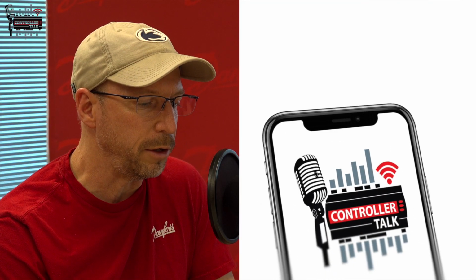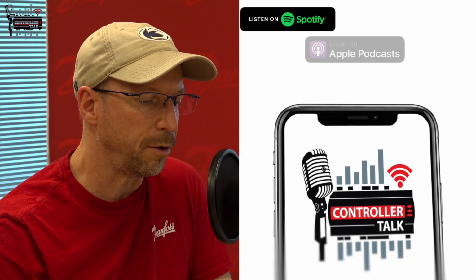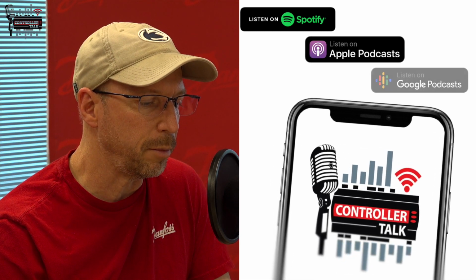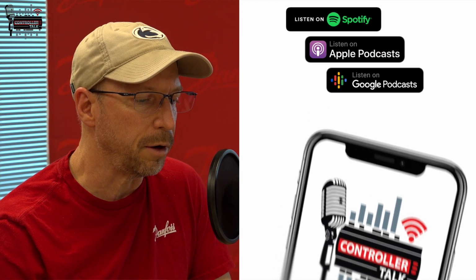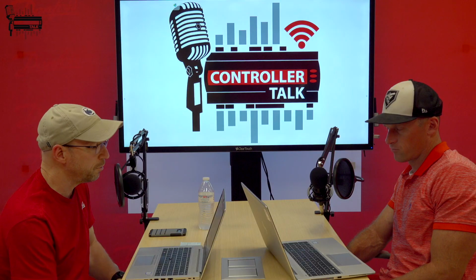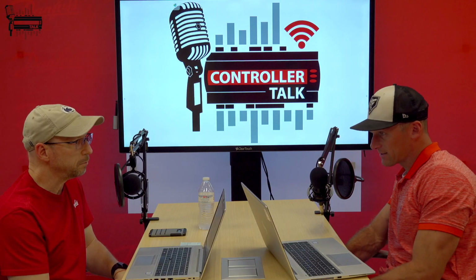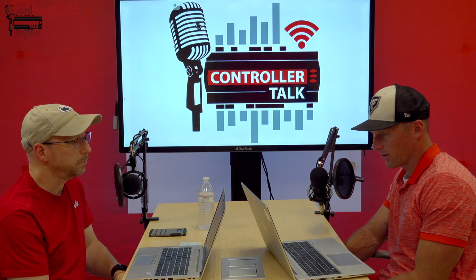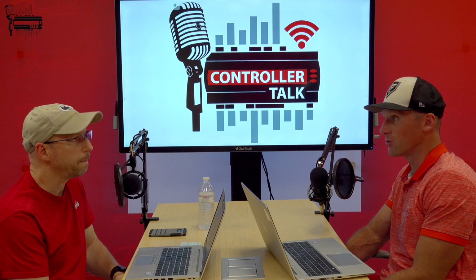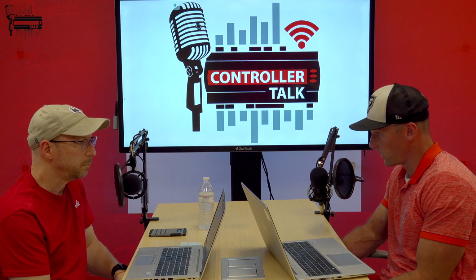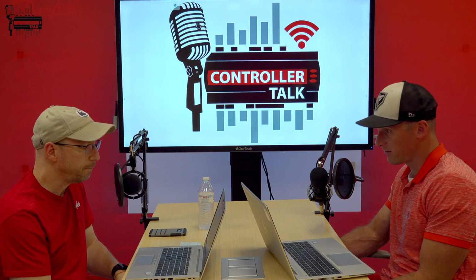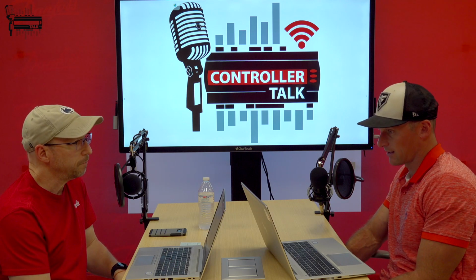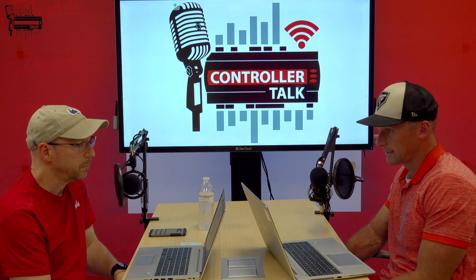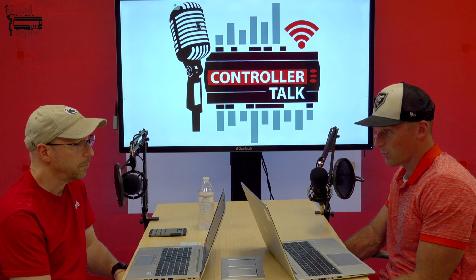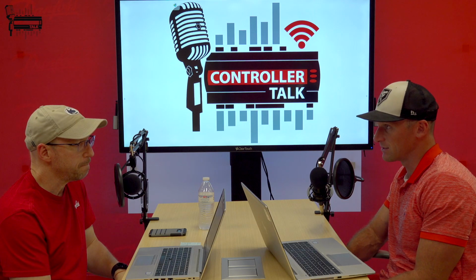And on these pack controllers, the max number of compressors increases up to 22, and then you still have your control, the high pressure valve, the receiver bypass valve, the advanced heat reclaim. All those things are an option. And then your max number of points goes from 120 up to 220 on this model. Yeah, and I'd say 90% of the racks coming out from OEMs today, if it's CO2, they're all booster for the most part, and they're going to have a 782 on it. Okay. So it's just the OEM selects the A or the B. That could come down to availability, what they had on their shelf. Mm-hmm. For us, it doesn't necessarily matter because, again, they control in the same way, everything tied to the rack. So, yeah, you probably go in assuming, if you're not sure, that the 782 is the one you're going to see on a job.